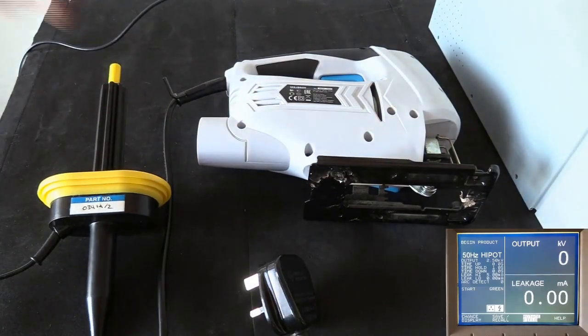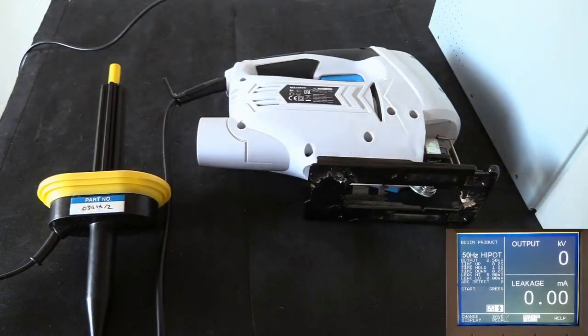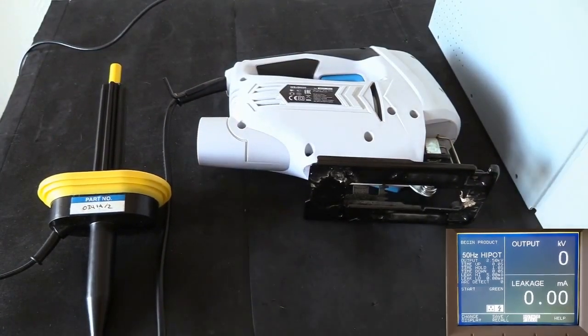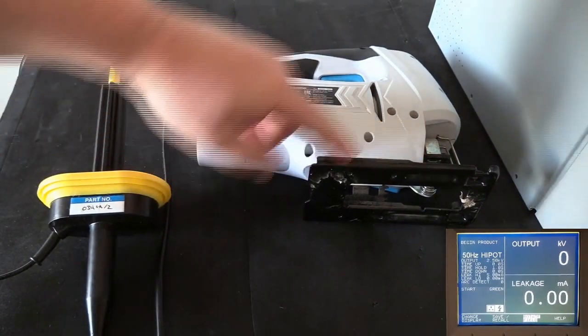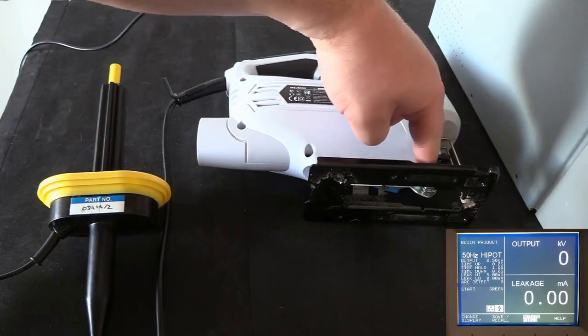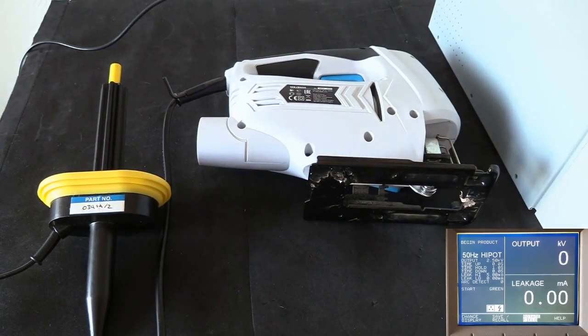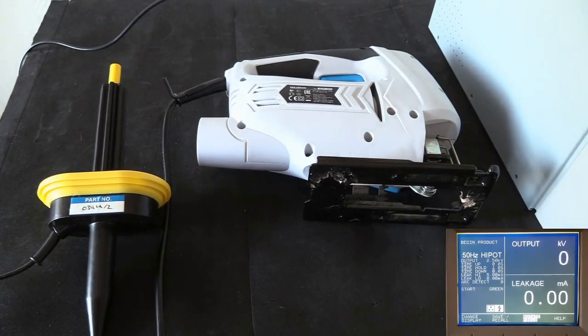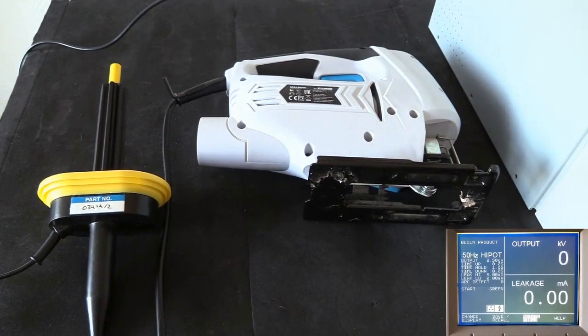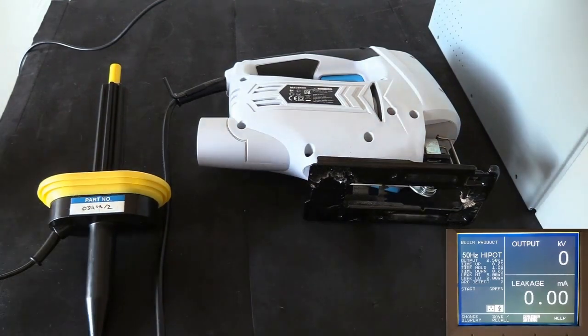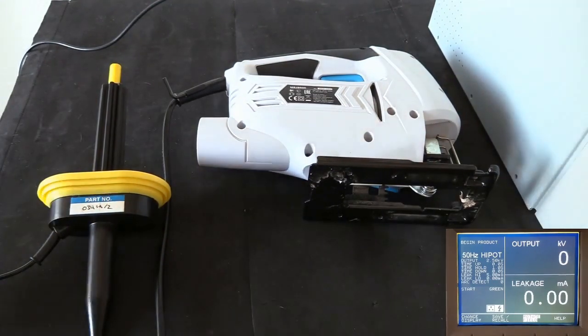So firstly, we need to connect our plug into our output box. And you'll notice there are various points on the device with exposed metalwork. So it may be that we have to perform the test multiple times to ensure that any exposed conductive parts are checked to make sure the insulation is good.